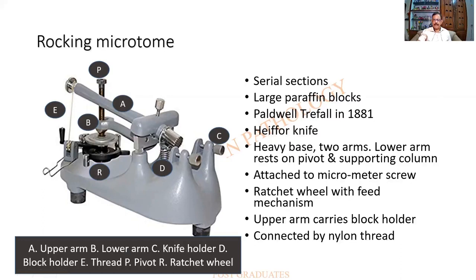Large paraffin blocks can be cut. It was designed by Caldwell and Trefall in 1881, and the knife originally used was the Heiffor knife. Its advantages include a heavy base, two arms, and the lower arm rests on a pivot attached to a micrometer screw. It has a ratchet and wheel mechanism; the upper arm carries the block holder, and all these are connected by a nylon thread.